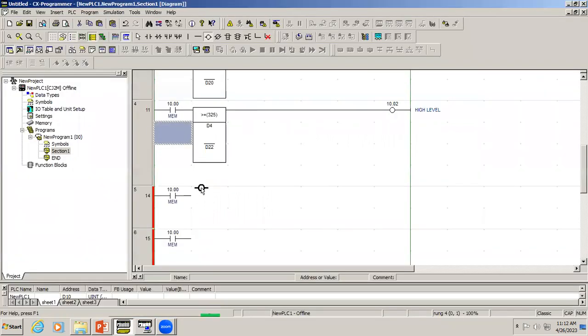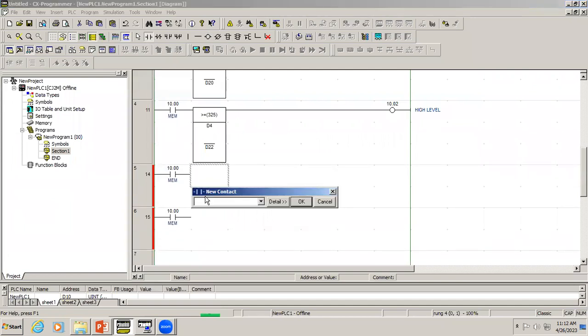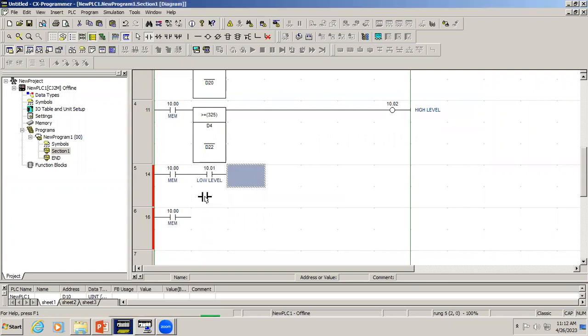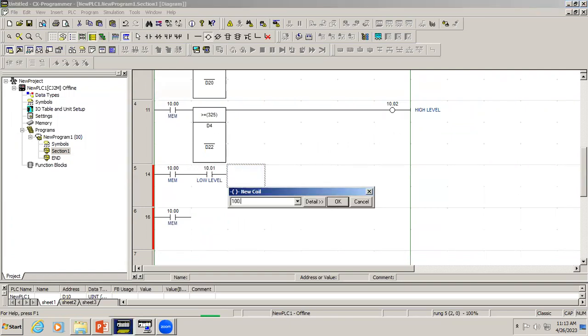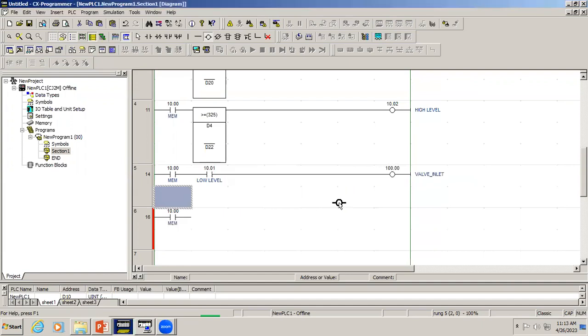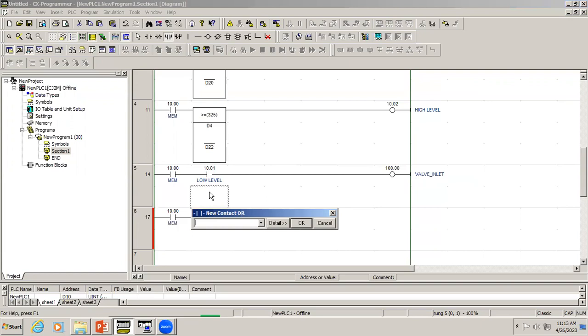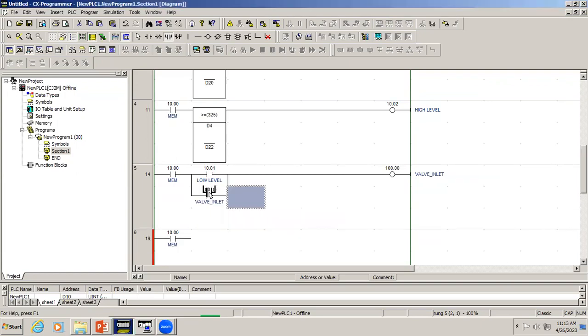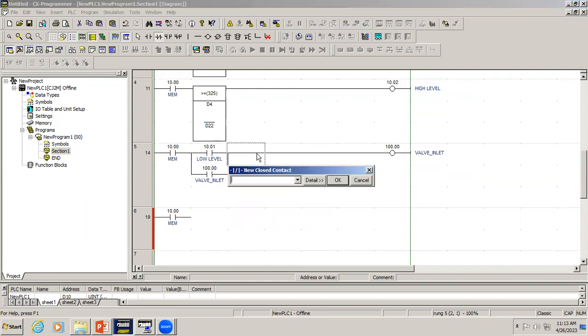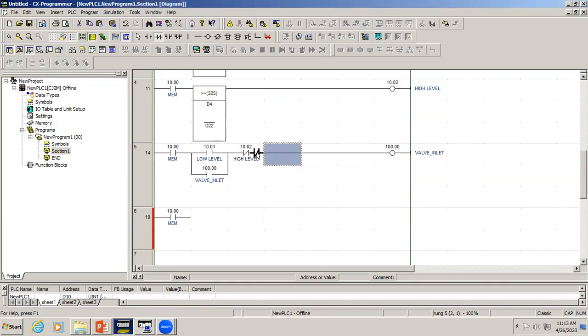So what I'm doing here is using the low level sensor connected to the inlet valve. If the level comes above that range, the valve should still remain open, so we have to implement latching. Once the tank reaches high level, the inlet valve should close.